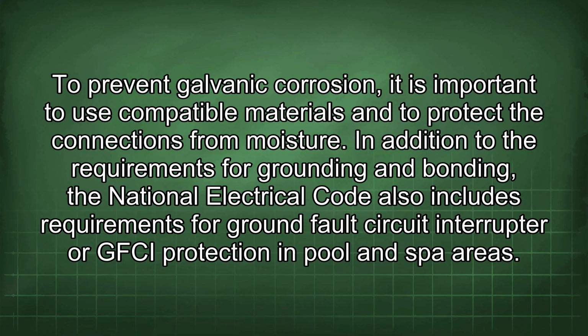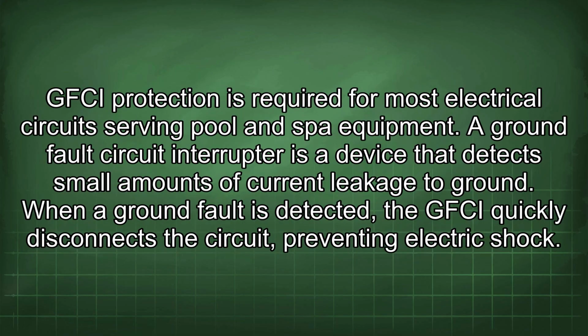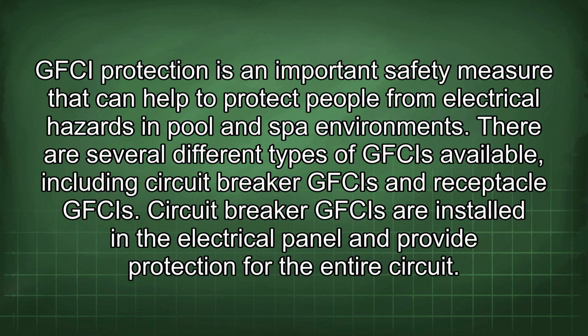In addition to the requirements for grounding and bonding, the National Electrical Code also includes requirements for ground fault circuit interrupter, or GFCI, protection in pool and spa areas. GFCI protection is required for most electrical circuits serving pool and spa equipment. A ground fault circuit interrupter is a device that detects small amounts of current leakage to ground. When a ground fault is detected, the GFCI quickly disconnects the circuit, preventing electric shock.